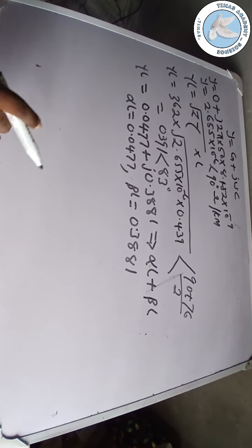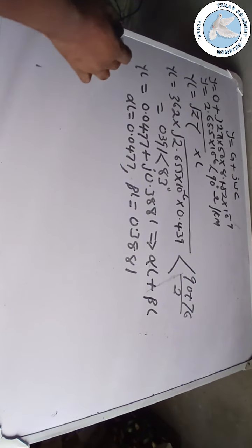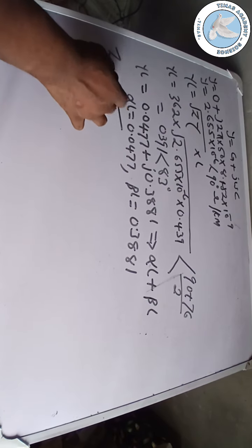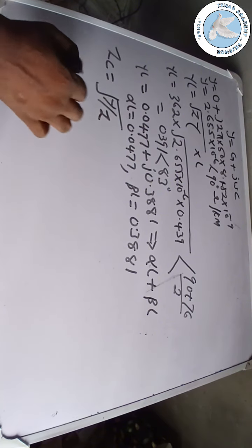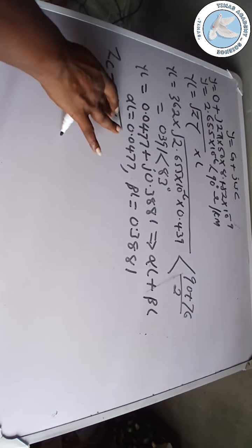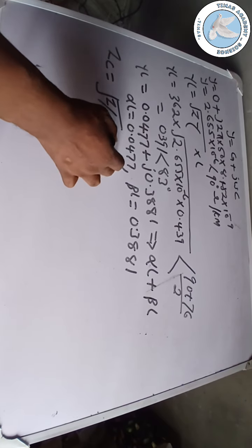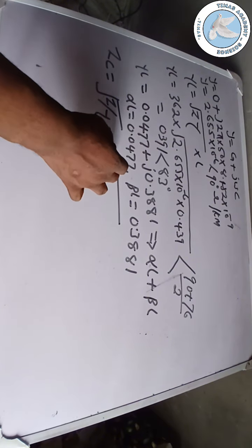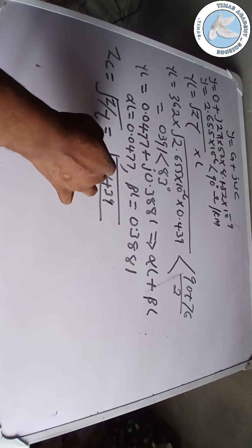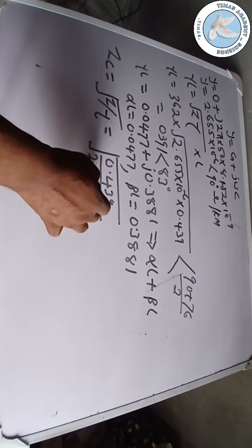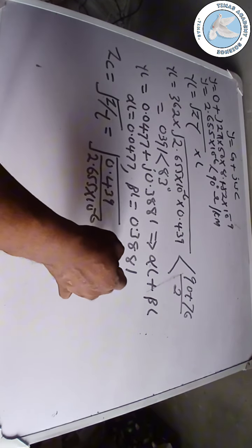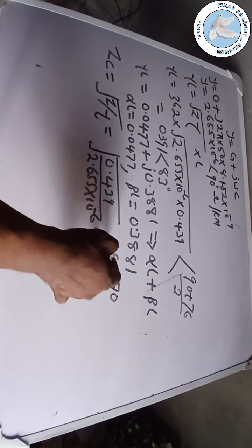We've gotten that. So the next one is the characteristic impedance. Characteristic impedance is the square root of the series impedance divided by the shunt admittance, and doing this we have the square root of 0.439 divided by 2.655 times 10 raised to the power of -6, and the angle is going to be 76 minus 90 degrees divided by 2.